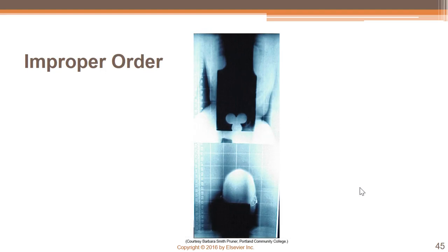This is another thing, and this also has to do with the processing. These were two plates used for spine imaging, but they were put in the processor in the wrong order. So you will find when you actually put them into the reader after you have taken the X-ray, then you say this is an AP spine. So then it has a certain histogram that creates the image from what you've told it was. But what they've done here is they've put the wrong things, so these are no longer usable. So just some more of those digital artifacts.